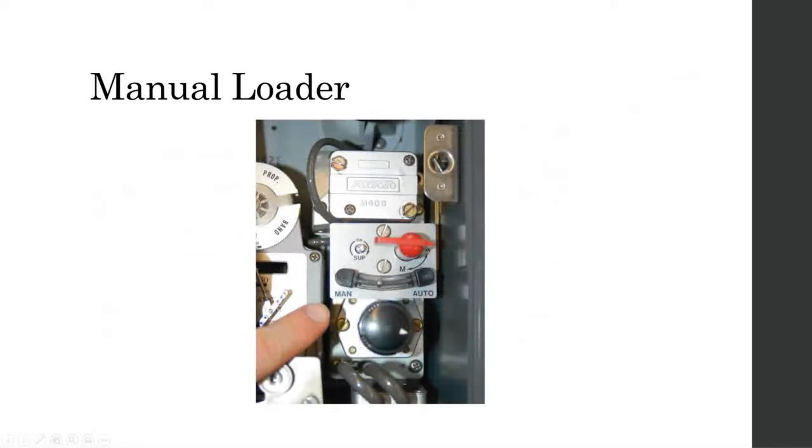This is what that manual loader looks like. And you see here, we've got the manual auto switch. So the idea here is you can vary the signal coming from the other controller. You get this ball to go in the middle point, and once that ball's in the middle point, you can make this switch and you're not going to get a bump.